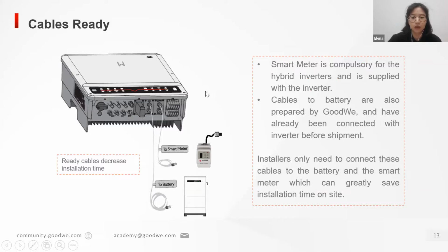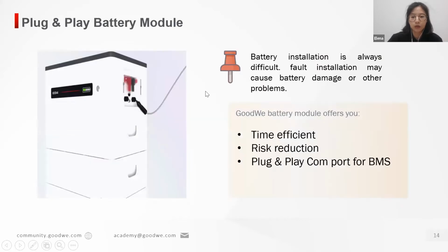For example, for the storage system, the smart meter is necessary. So the smart meter will be supplied with the inverter, and the cables to the meter and also the cables to the battery are also prepared by GoodWe. Installers only need to connect these cables to the battery side and to the smart meter side, which can greatly decrease installation time on site. So for the on-grid inverter, we only need to connect the DC and AC cables and the communication cable.